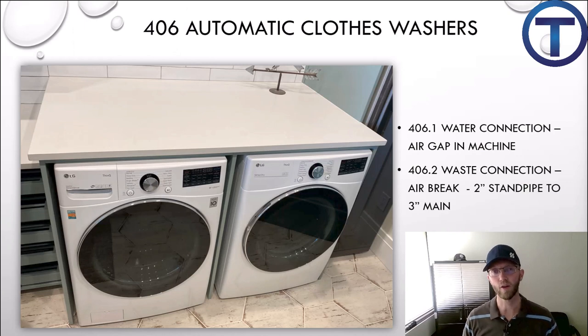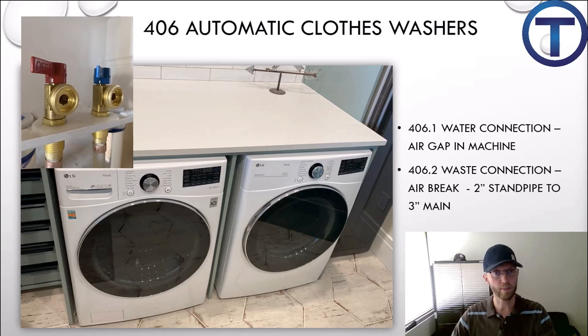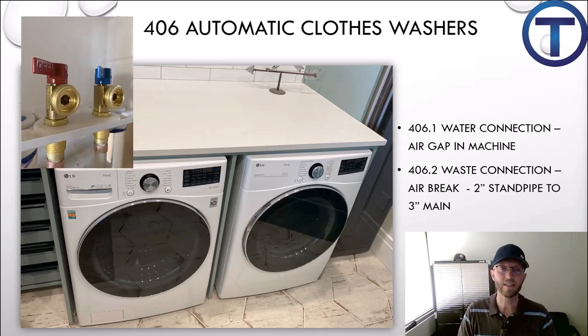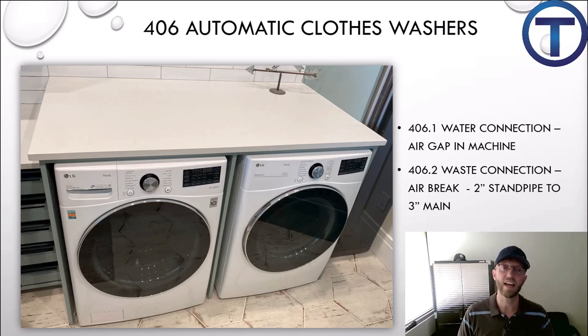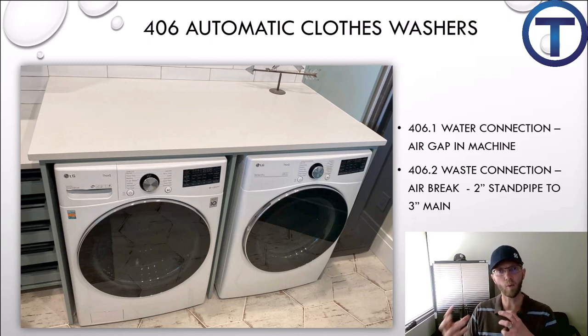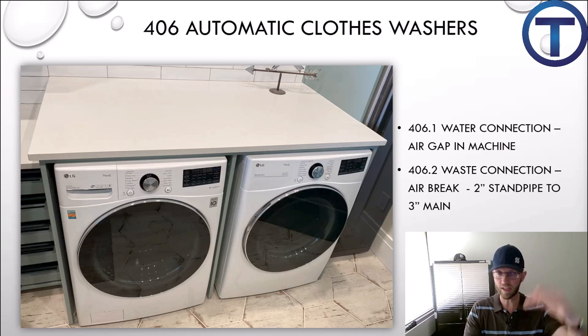406 is about automatic clothes washers. 406.1 covers the water connection and 406.2 covers the waste connection — those are the two main plumbing connections to any washing machine. When we hook up the water to a washing machine, that washing machine has to have an air gap built in. The air gap protects our potable water against backflow from drainage. This air gap is actually built into the machine where the water flows into the barrel that washes the clothes. That's not something you have to install, but it is a code requirement.